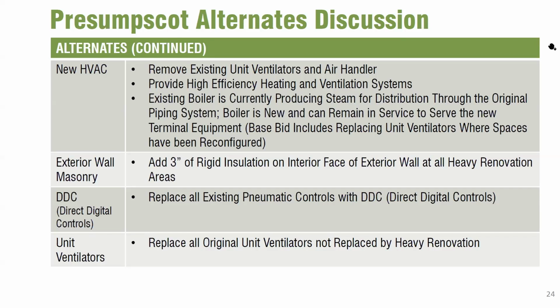I'd like to add, as we look at Presumpscot and schools like Reiki in their ages, this technology was installed in the late 70s, early 80s. There's a tremendous difference in equipment today. In particular, if we could go to a condensing hot water system from that boiler rather than steam, there's opportunity to retrofit unit ventilators the same size as what you see in your rooms now, potentially allowing energy recovery and variable refrigerant flows within the same unit, which simply means heating and air conditioning.